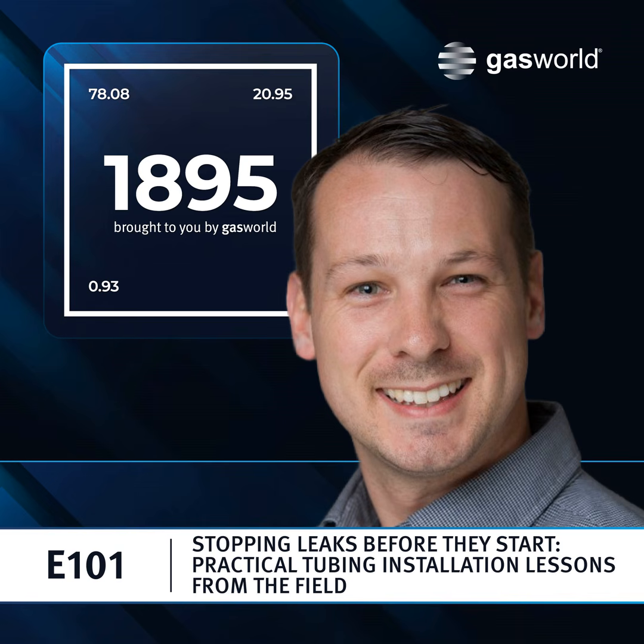So, once you're installed, some of the things we also see are tube support issues that, while that may not create a leak right from the start, it creates some long-term challenges for your installation by creating opportunities for vibration to take hold, crevice corrosion or different corrosion challenges around those spaces if the tubing's not properly run in the right way, those types of things.